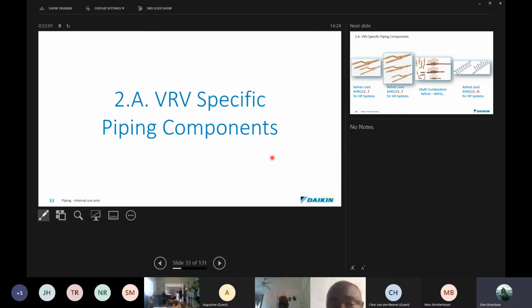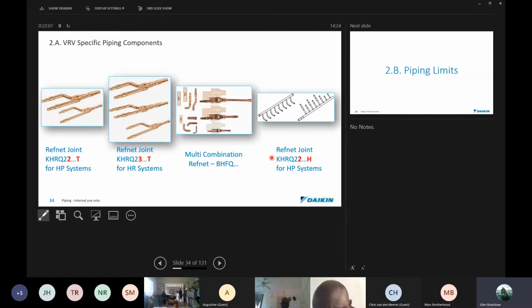In piping, specific piping components, the shortest part of this talk this afternoon. Okay, basically, we have RefNet joints. So RefNet joints, the first 2 images, the first one for a heat pump system, which only has 2 pipes in it, 2-pipe system, and a 3-pipe system where a RefNet kit will come with 3 RefNets in it. Okay, you'll notice the RefNets step up in sizes. You need to cut these back to the size piping that you're working with. Okay, don't go and push the piping over and leave the longer end in if you need to cut it further back over here. It must be cut back to the size that you're working on.